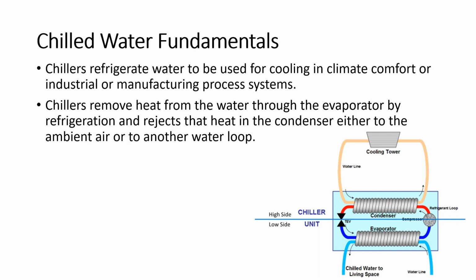The low side has the evaporator, that's where the refrigeration cooling happens, and the high side is the condenser where we reject the heat, and that's always common. But you have one side versus the other. We use the terms interchangeably, so we talk about high side and low side. It just means evaporator and condenser.